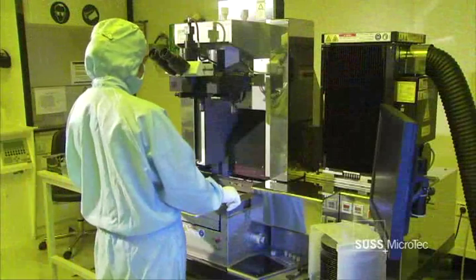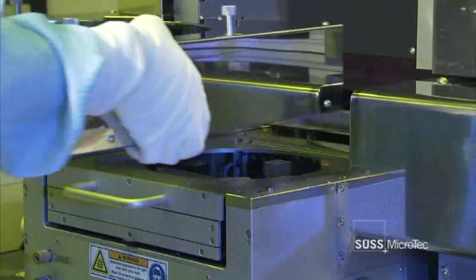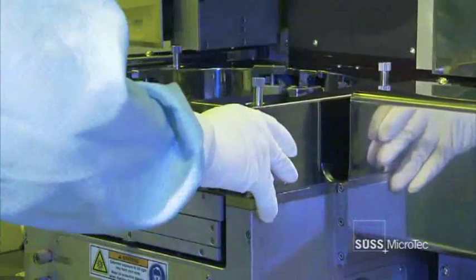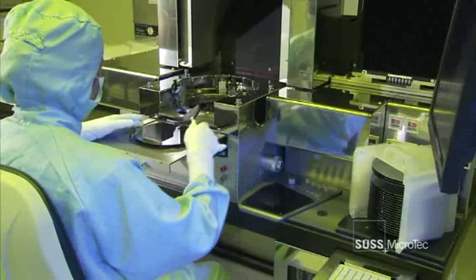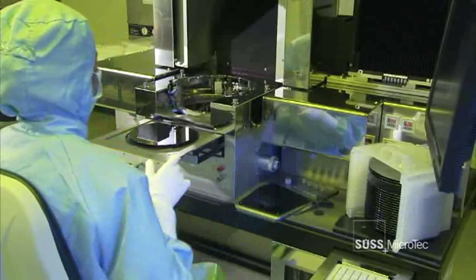SUSS offers the research community a highly accurate and versatile system that supports a variety of innovative process technologies. Switching from photolithography to any other technology is fast and easy. Bond alignment applications just require the exchange of an adapter frame. The BA8 Bond Aligner aligns all wafers and substrates precisely, prior to the wafer bonding process performed in a SUSS wafer bonder.